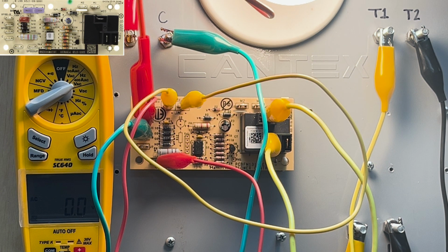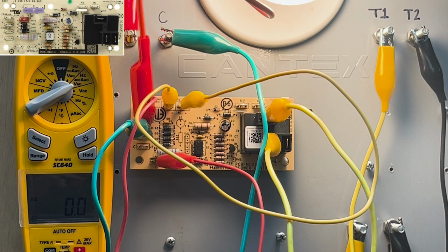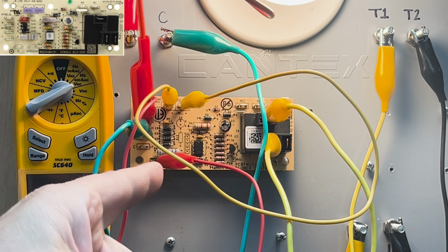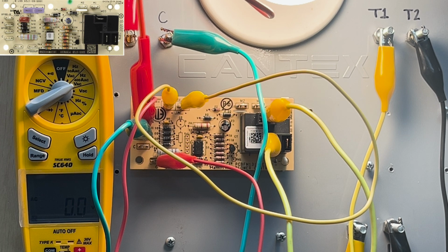And anytime you have a fuse that's blown, you want to replace that fuse with the same size fuse. So don't go down to the auto parts store and say, oh, I found a fuse that'll fit, and it winds up being a 7.5 amp fuse or a 10 amp fuse or a 15 or 20 amp fuse, because you're not going to do anything more than what I'm doing here. So don't do that. You want to just leave it down until you get the right size fuse, and then you want to find out what's causing your short. It doesn't mean that the board's bad. Your short can be anywhere in the low voltage systems. We recommend getting an experienced HVAC company out there to troubleshoot that.